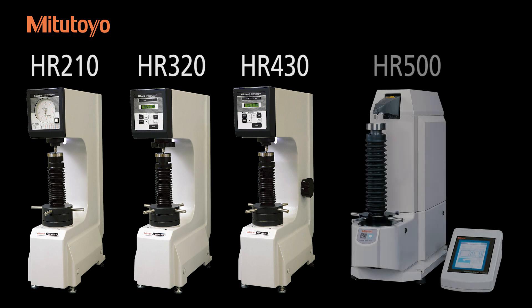The last type is our HR-500 series, which features a similar brake start design but also includes a closed-loop electronic loading system, as well as control over all test parameters, such as loading speed and scale selection.